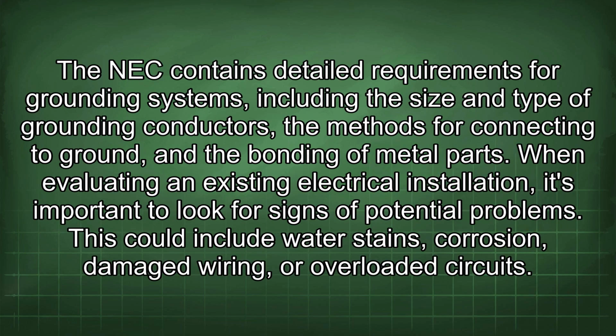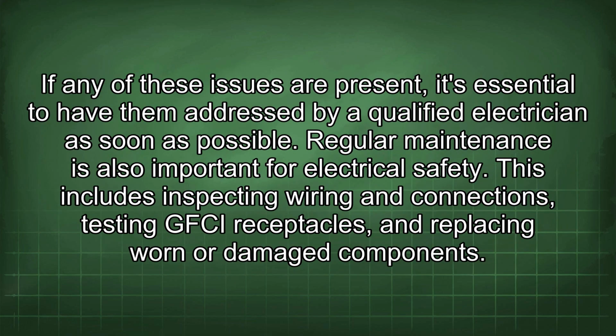The NEC contains detailed requirements for grounding systems, including the size and type of grounding conductors, the methods for connecting to ground, and the bonding of metal parts. When evaluating an existing electrical installation, it's important to look for signs of potential problems. This could include water stains, corrosion, damaged wiring, or overloaded circuits. If any of these issues are present, it's essential to have them addressed by a qualified electrician as soon as possible. Regular maintenance is also important for electrical safety.